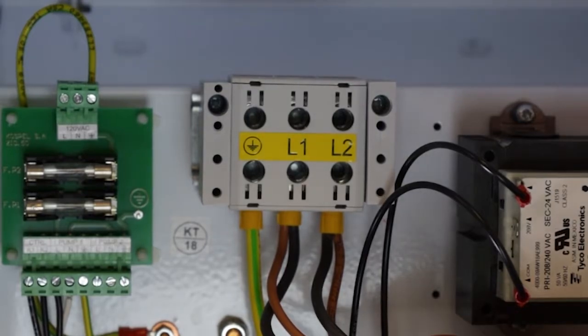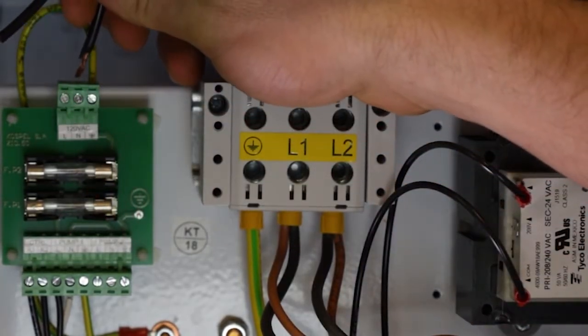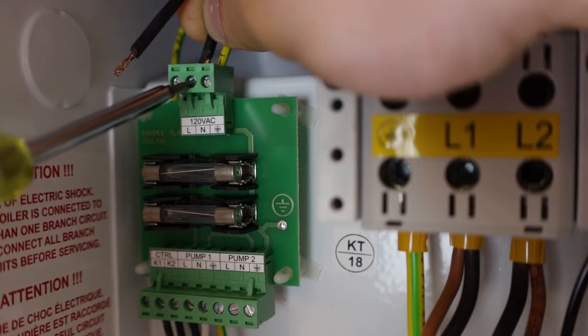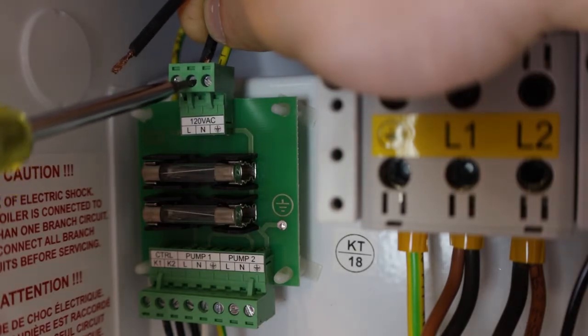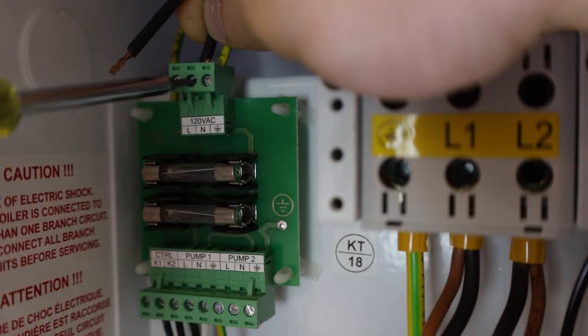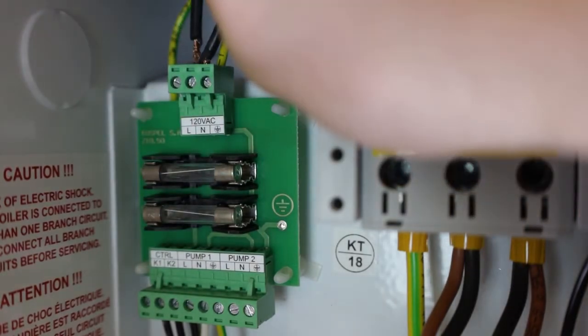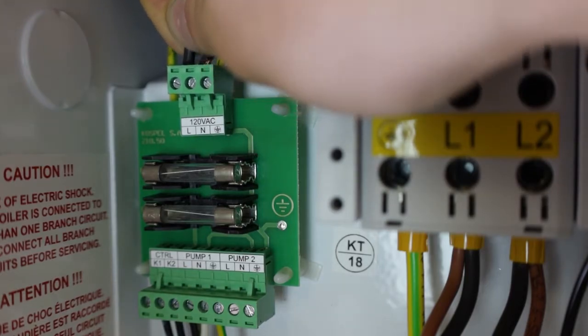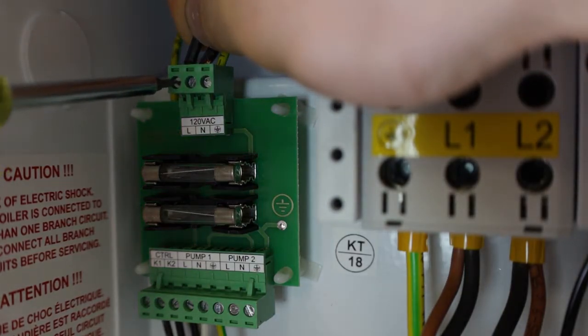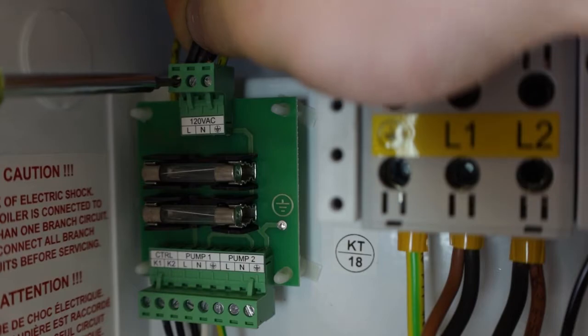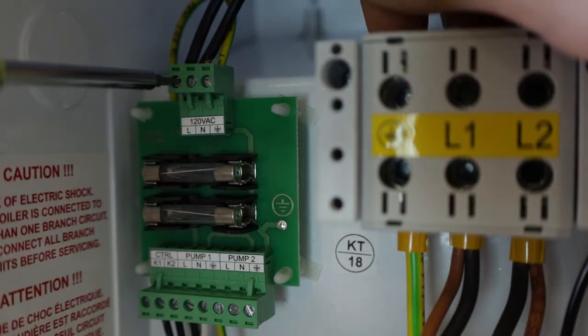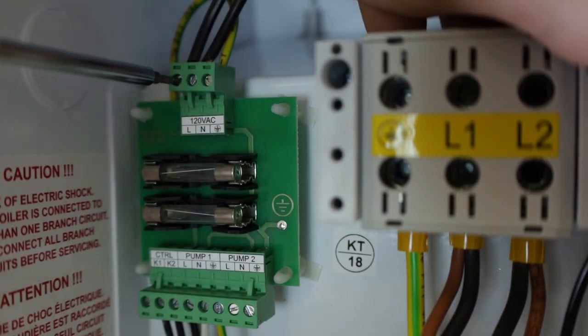Next, prepare to connect the separate power source for the circulating pump. The circulating pump requires a 120 VAC 15 amp electrical circuit. If your hydronic system requires a secondary pump, utilize the pump 2 connection to operate the second pump. This is located below the 120 VAC power source. Extra fuses are taped inside the boiler.